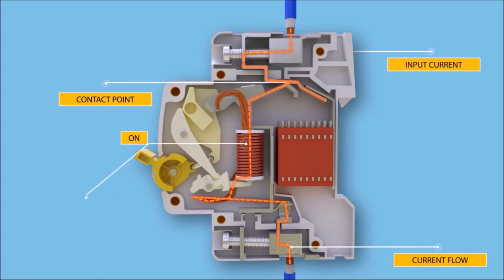The current path goes through: first the incoming terminal, then the contact point of moving and fixed contacts, then the magnetic coil, then the bimetallic strip, then the outgoing terminal. All are arranged in series.